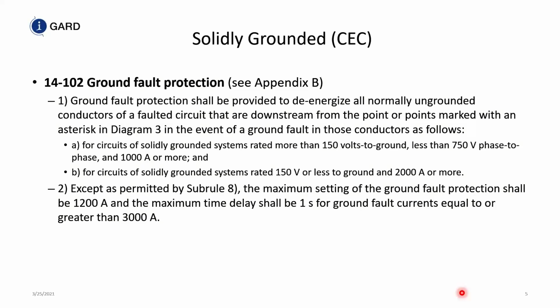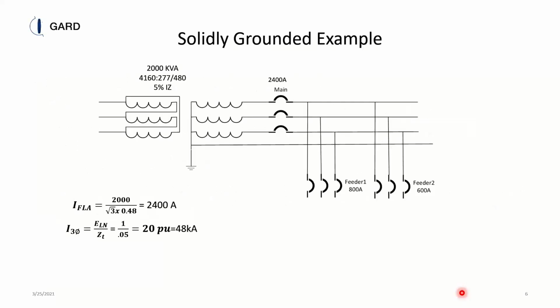So the Canadian Electrical Code has the same thing. 150 volts to ground, 750 volts phase to phase, 1,000 amps or more. And it basically says the same thing: 1,200 amperes, 1 second maximum for a ground fault current not less than 3000 amps.